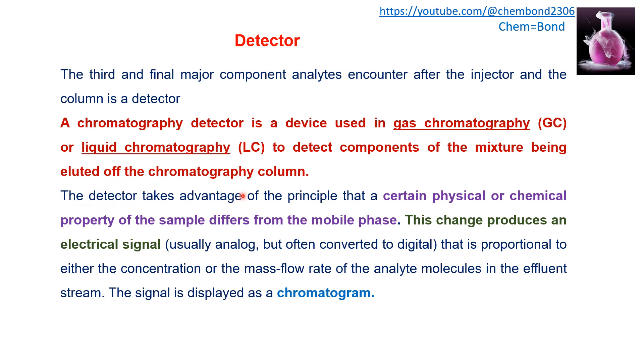A detector takes advantage of the principle that certain physical and chemical properties of the sample differ from the mobile phase. There are differences in physical and chemical properties between the mobile phase and the sample. This change in property produces an electrical signal proportional to either the concentration or mass flow rate of the analyte in the effluent stream, and that signal is displayed in the form of a chromatogram.